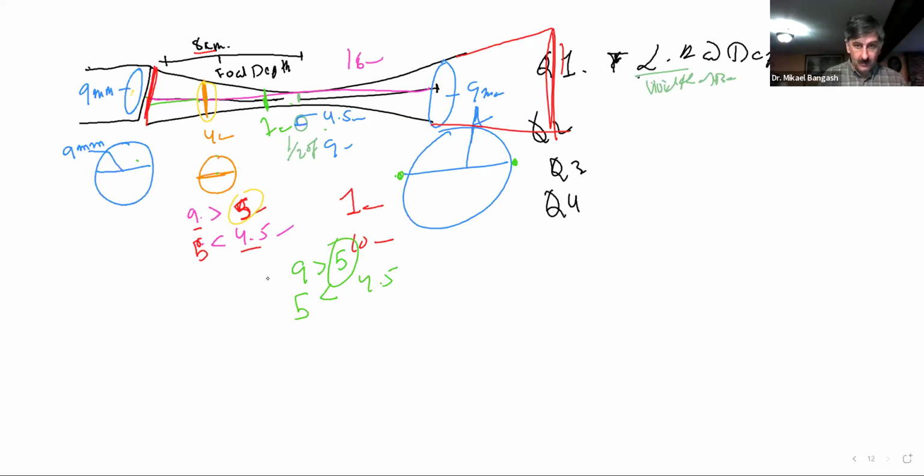Now the next question, question number 5. It asks, what is the best estimate for the lateral resolution at 20 centimeters or 21 centimeters? Clear for me, that's going to ask what will be the width of the beam at a depth of 21 centimeters.